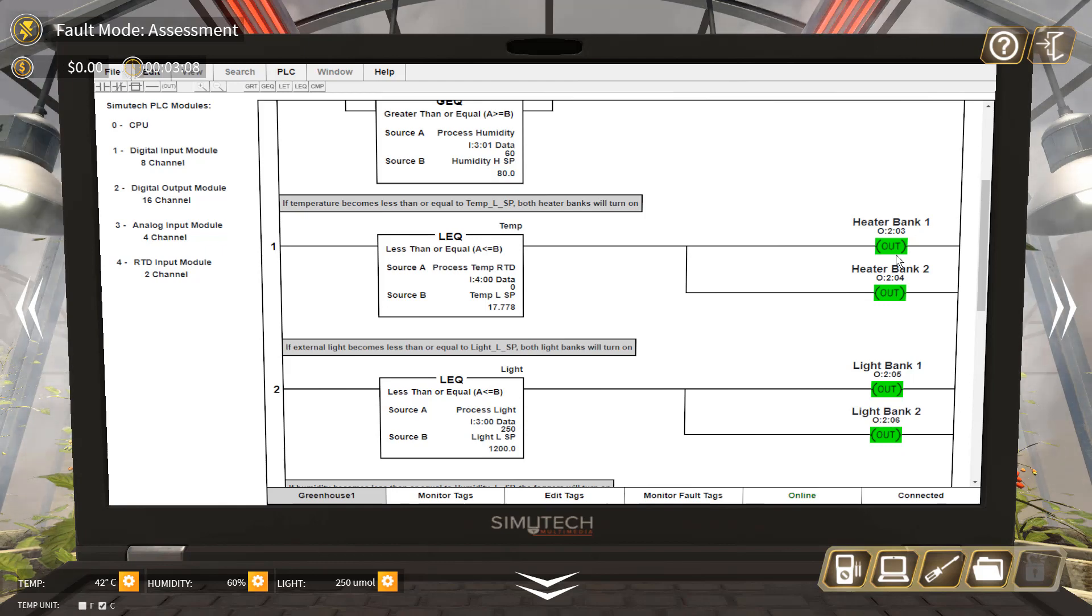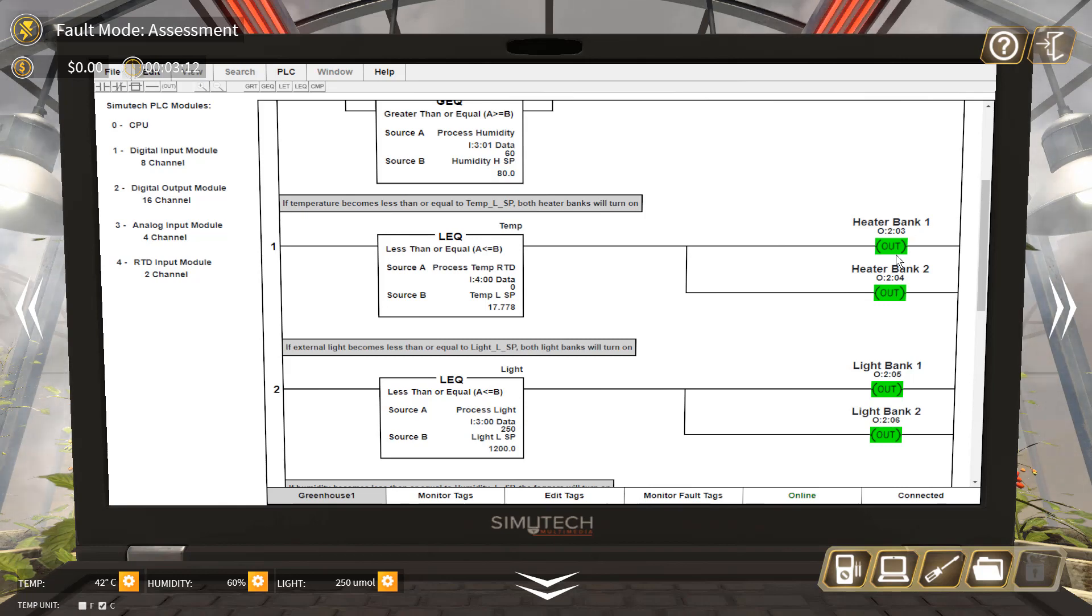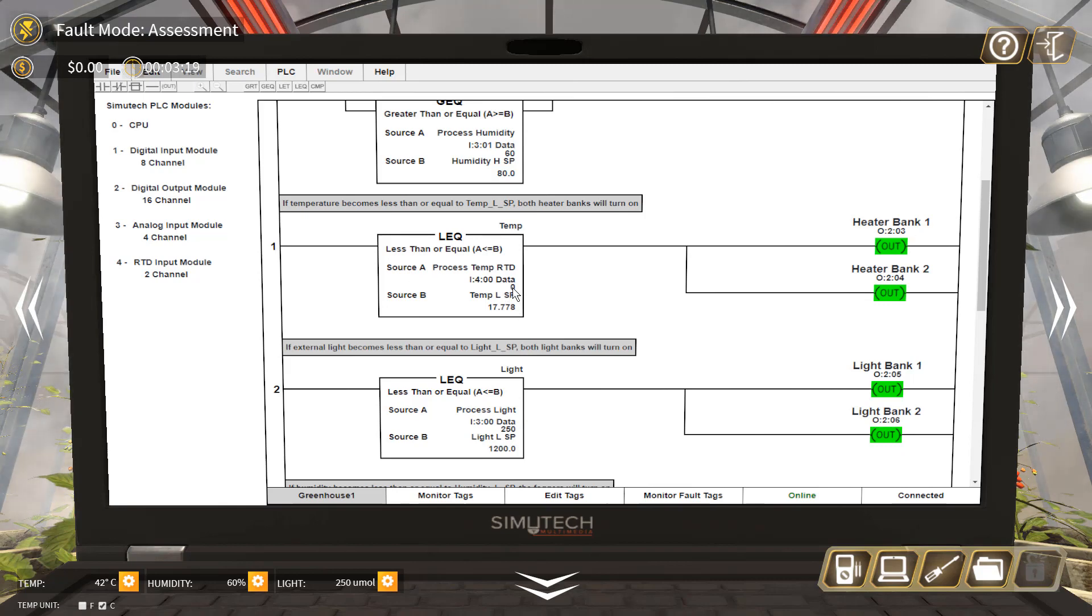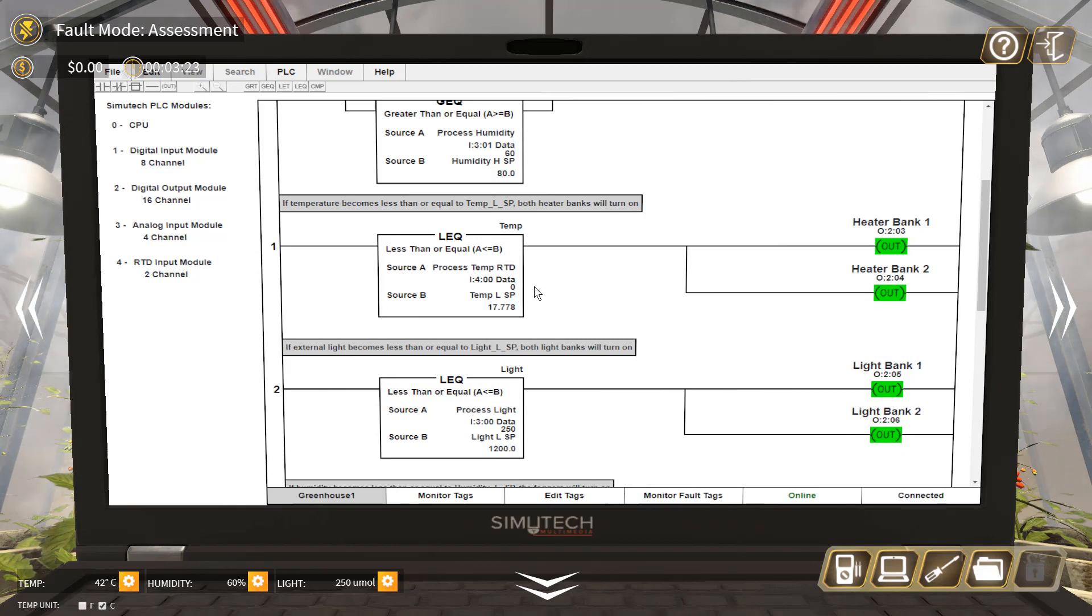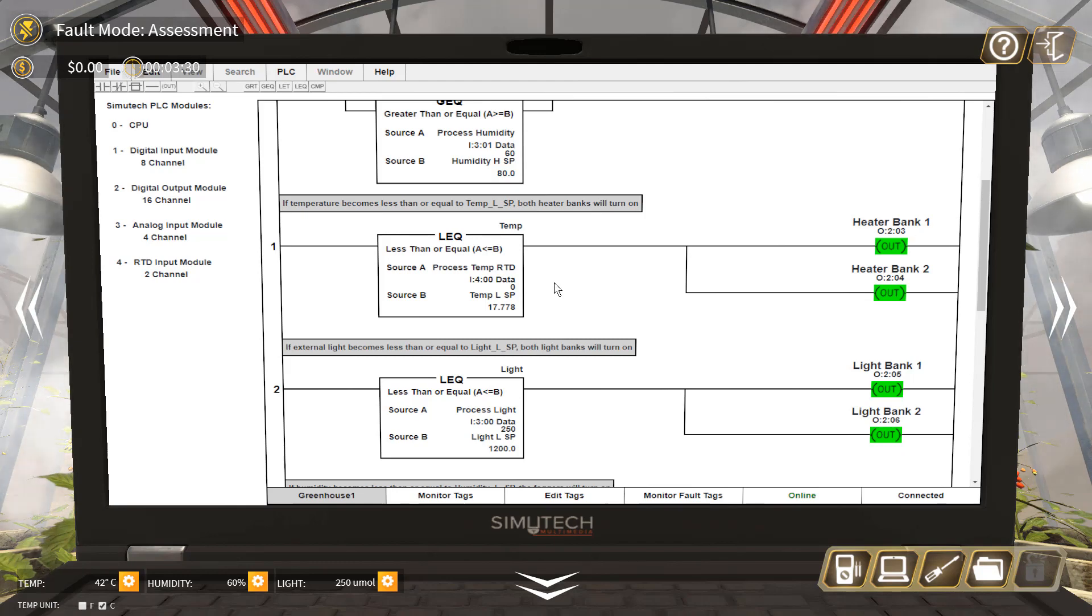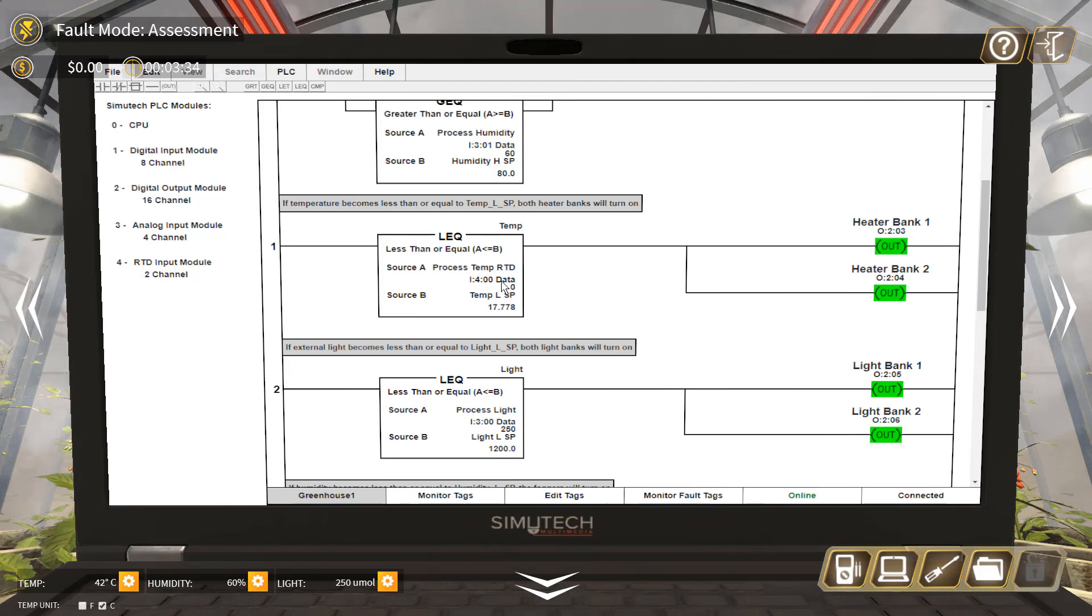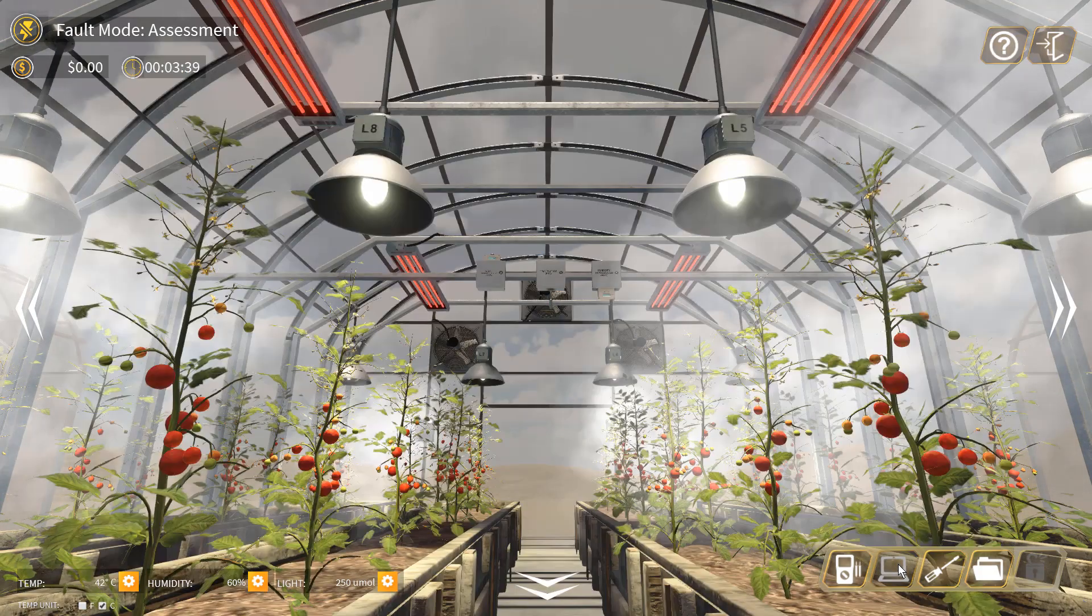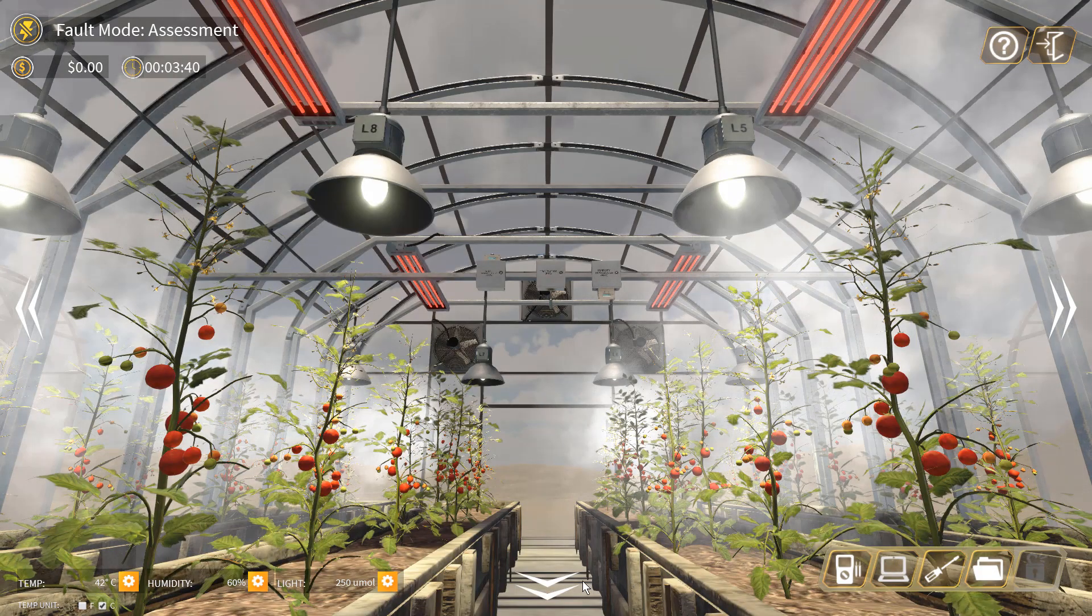In this case, source A is the temperature, which shows zero - which is wrong because it's supposed to give 42 degrees Celsius as it takes the temperature reading from the RTD and feeds back to the PLC analog input RTD module number 4 channel 0. If you do not have access to PLC, you can use the drawing to find out the problem.